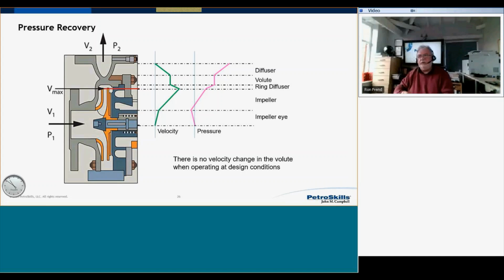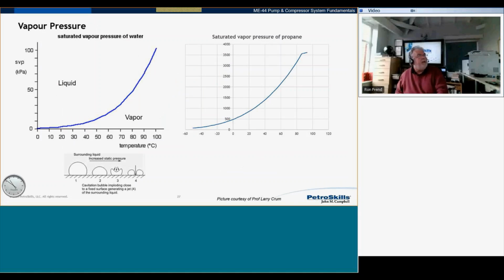I'm not going to go through too much of this. I'm going to skip quite a few of these now because I've got some information here about cavitation. And I'm sure everybody here knows about cavitation. Every liquid will vaporize, it will flash at a particular combination of pressure and temperature. If you go from this side of the vapor line to that side, you're flashing from a liquid to a vapor. Going back again, those bubbles of vapor collapse, and that is cavitation. And that can be extremely damaging.